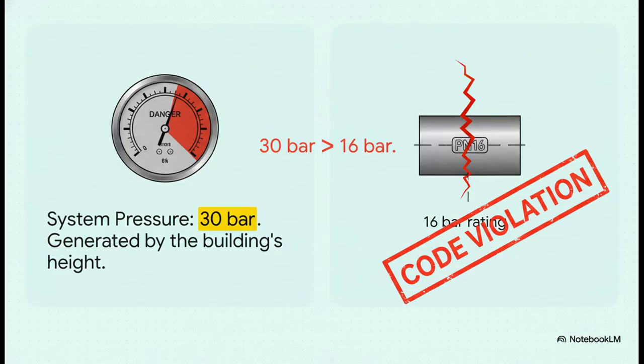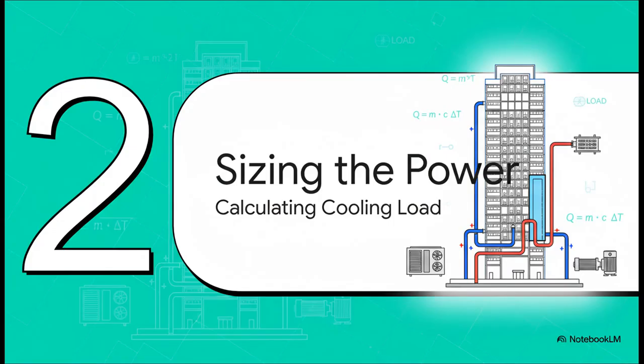And this right here, this is the whole problem in a nutshell. Standard, off-the-shelf pipes and components are often rated for PN16, which means 16 bar. But our system is creating almost double that. So trying to run one single pipe loop from the basement to the roof isn't just a bad idea, it's a huge code violation according to standards like SBC 501 and ASHRAE. It's not allowed, period.